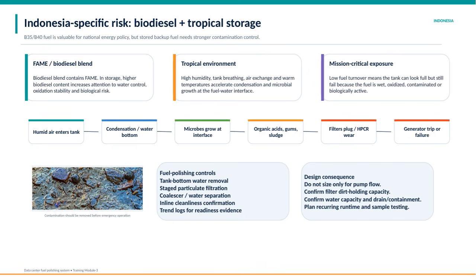One critical risk with stored backup fuel is that tanks may appear full, but the fuel inside could be compromised, wet, oxidized, or biologically active, leading to potential generator trips or outright failure during an emergency. To mitigate these risks, contamination must be removed proactively before emergency use. Effective fuel polishing techniques include removing water from the tank bottom, staged particulate filtration, and using coalescers or water separators. Continuous inline cleanliness checks and trend logging help ensure the fuel remains ready and reliable.